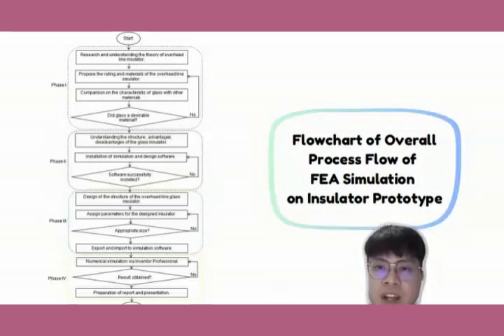Phase 1 is about the research and understanding stage, where the rating of the transmission system and the type of overhead line insulator are proposed. Not only that, a comparison between the glass insulator and other types of insulator is conducted to determine the pros and cons of the glass type insulator for a 275 kV transmission system.